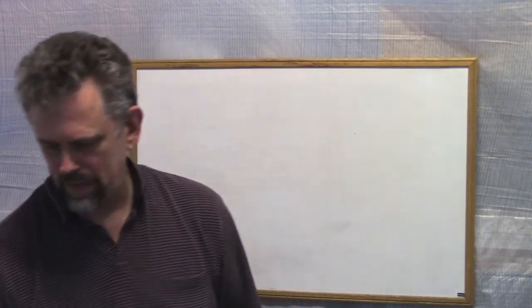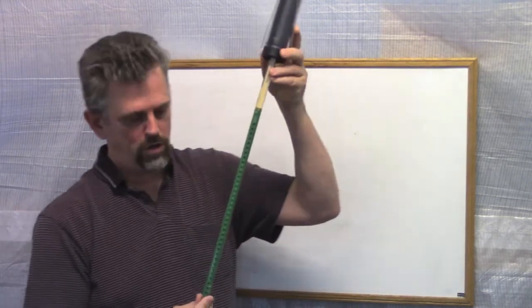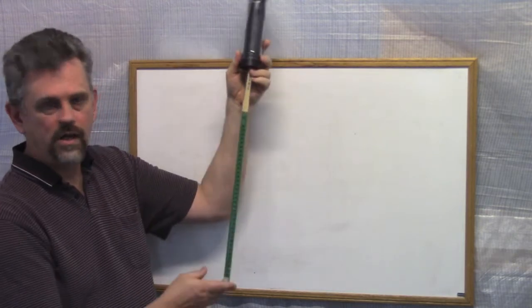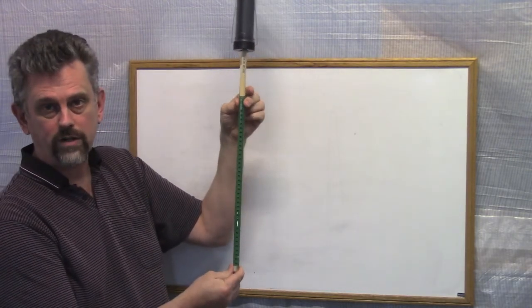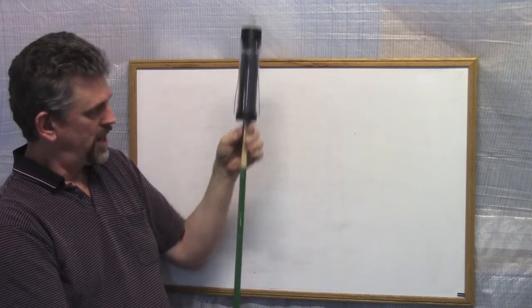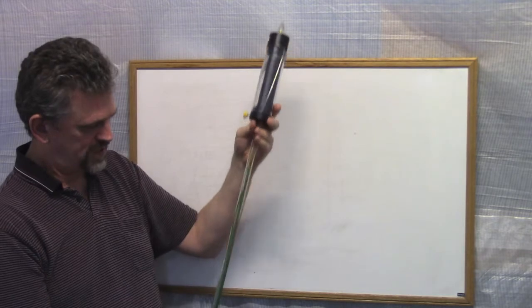And I remember the instrument, the Sedimeter, but of course that Sedimeter was a bit clumsy. So I designed a new version with a longer sensor. This is Sedimeter second generation. It has 36 optical backscatter detectors instead of 16, and a much smaller house because it's using more modern electronics. It doesn't take so much space.